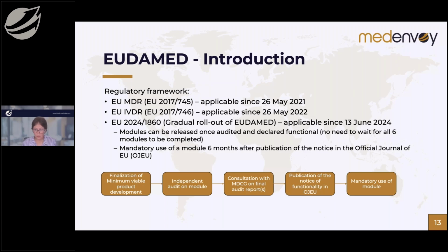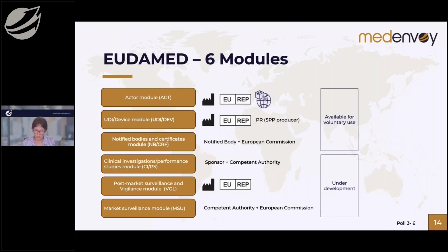So looking at EUDAMED, it consists of 6 modules: an actor registration module, a device registration module, a module in which notified bodies are identified and can upload related certificates. There will be a module related to clinical investigations and performance studies. There is a module on post-market surveillance and vigilance, and there is a market surveillance module dedicated to the competent authorities and oversight by the European Commission.